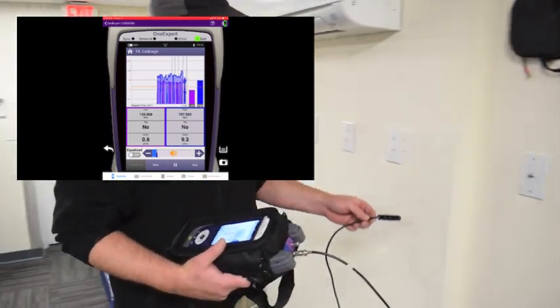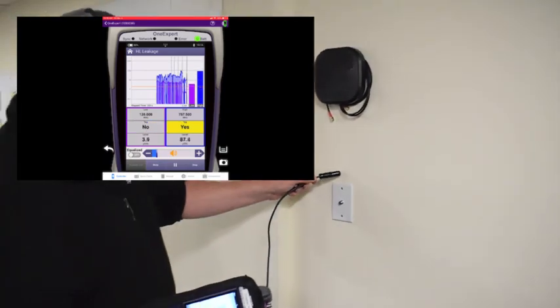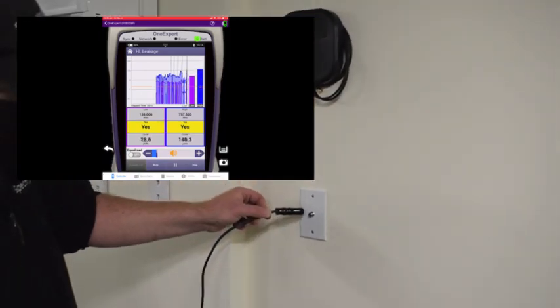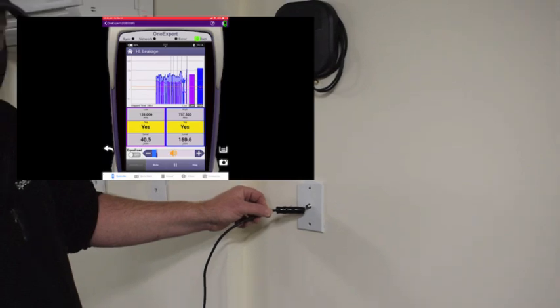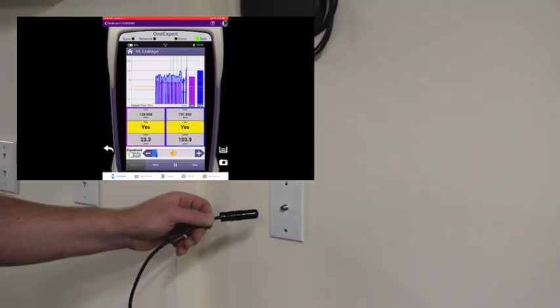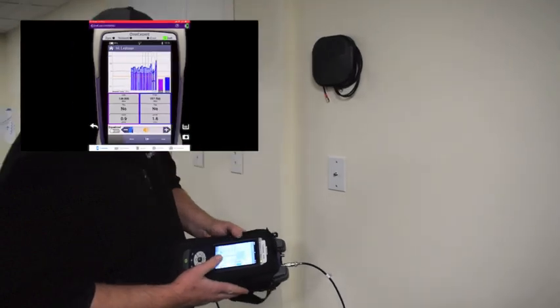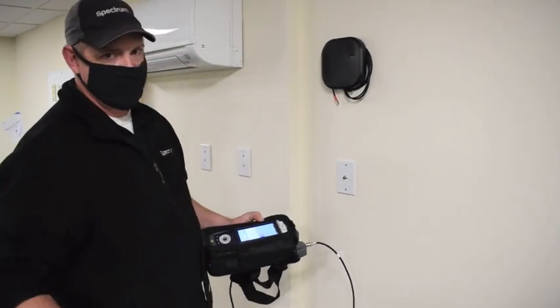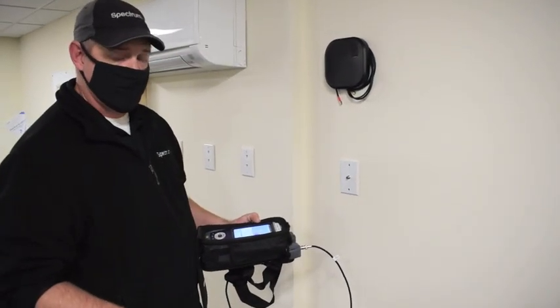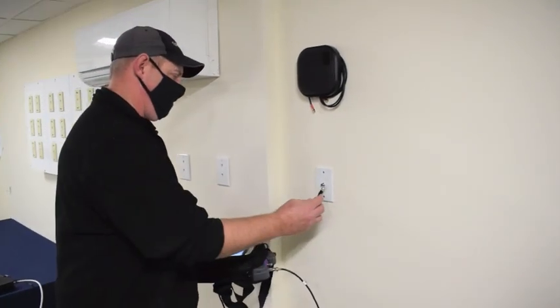Moving over to the unused outlet, I'm able to see that the actual leak is coming from the unused outlet. Okay, now to make the repair, I'm going to pause the test. I'm going to terminate this outlet. Any outlet not being used should either be terminated or disconnected.